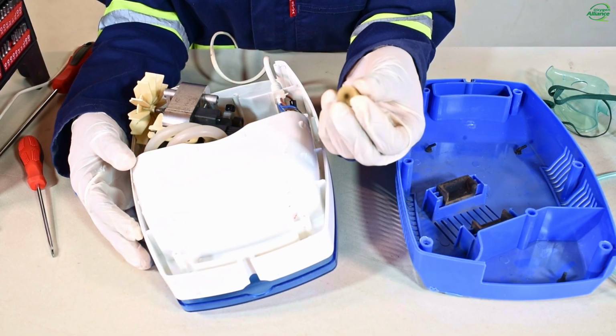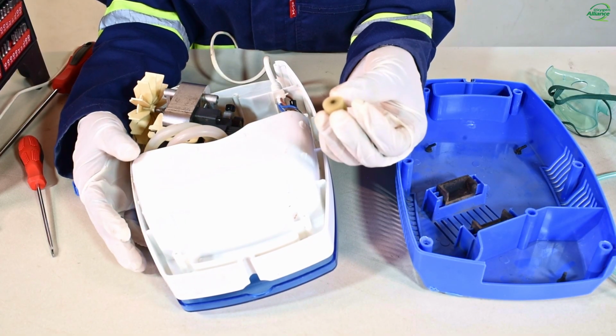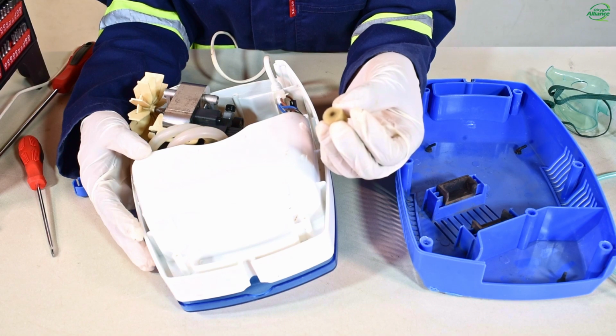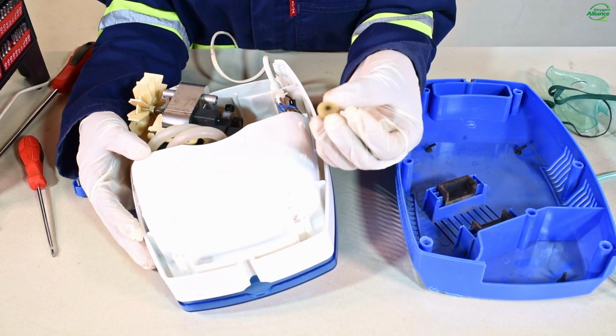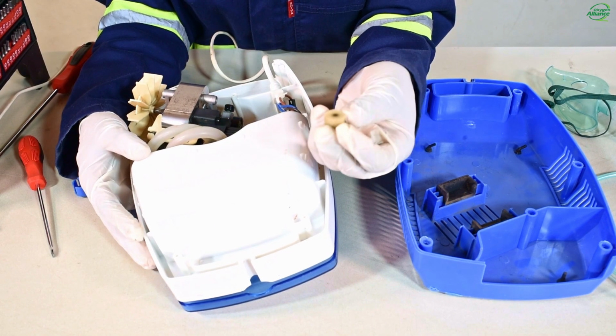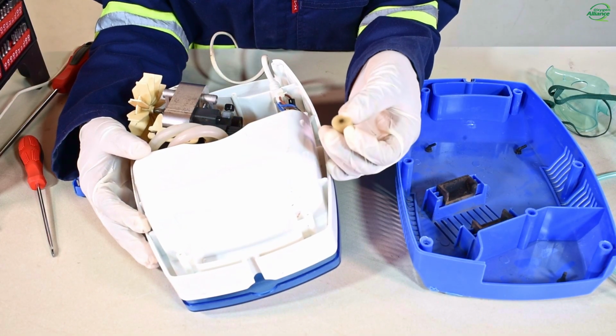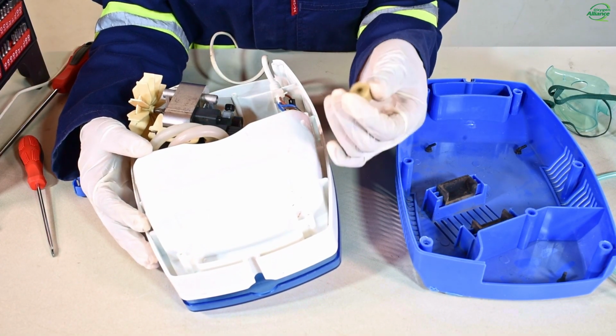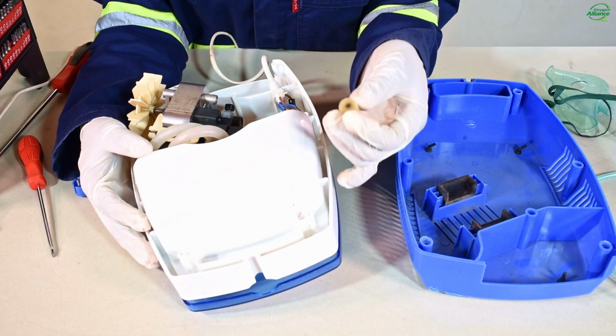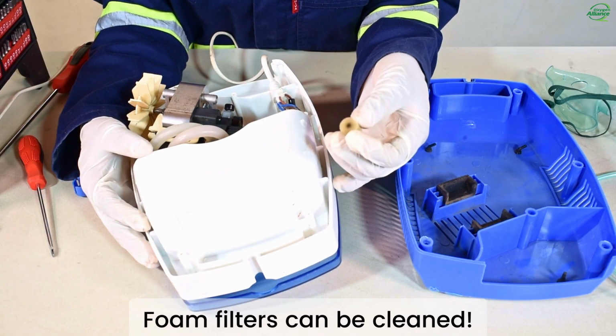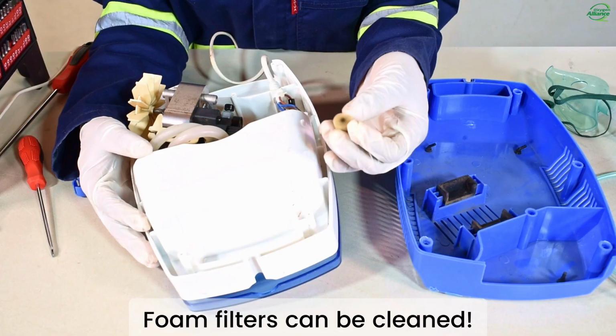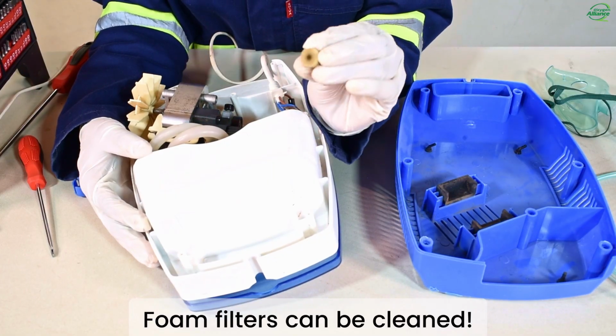This results in low or no pressure supplied to the nebulizer kit. With low pressure, there will be no mist production. If the filter is dirty, it is recommended that it should be replaced. However, depending on the type of filter, you may just clean it. For example, with this filter.